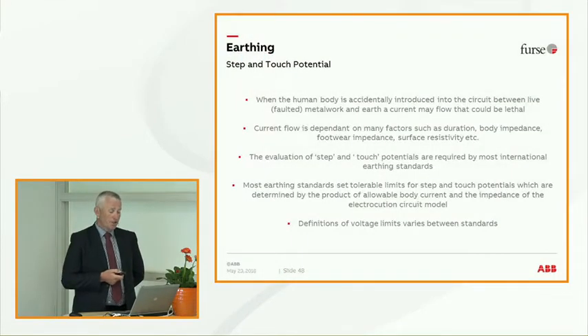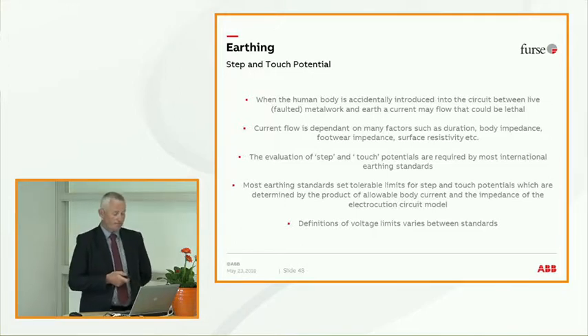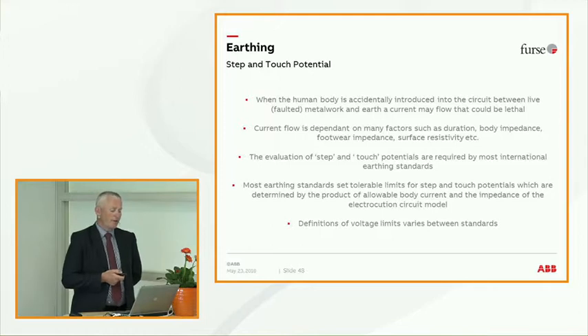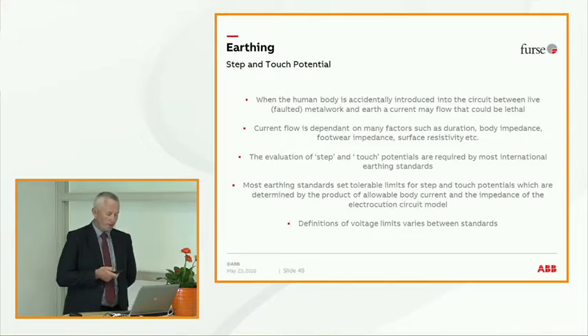Briefly on step and touch potential, it's when the human body is accidentally introduced into that fault current. The current flow is dependent on many factors. This can be the footwear the guys are wearing, this could be chippings, rocks around a site. Most earthing standards set tolerable limits to work to. And again, it's all about the loss of human life. It's regarding the standards that you're working to.